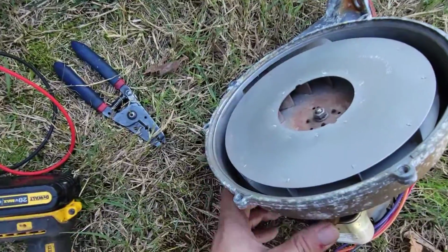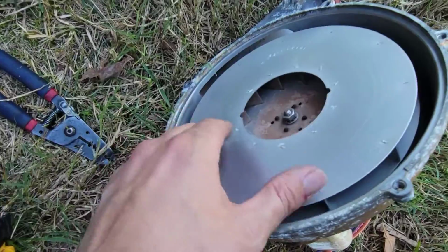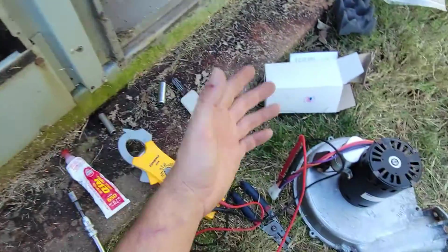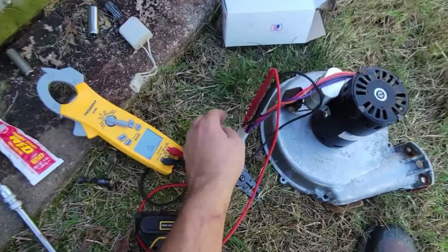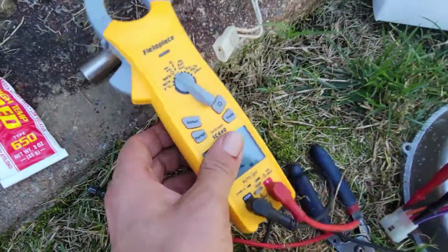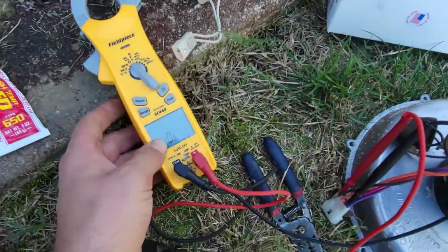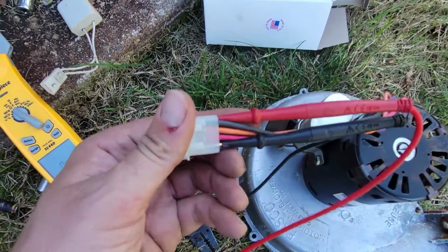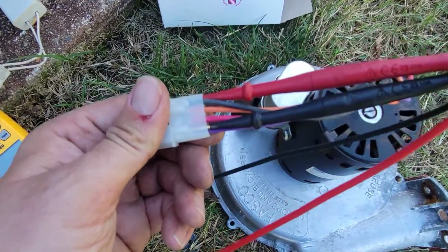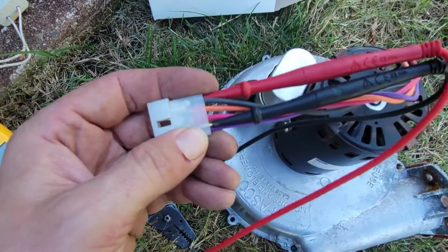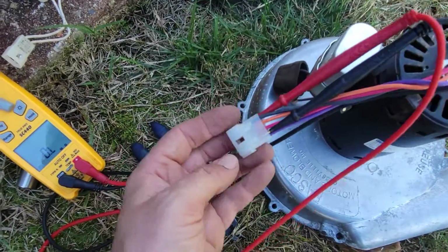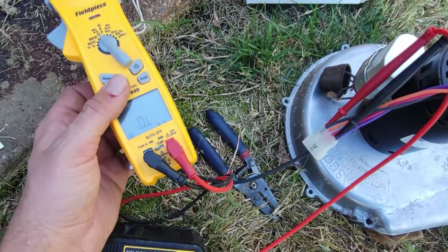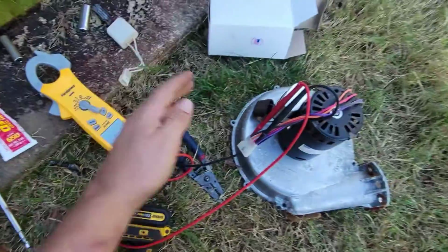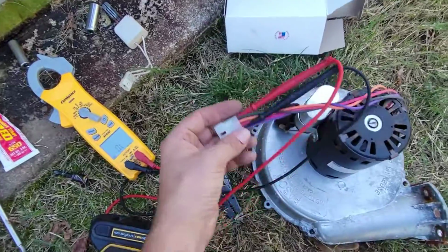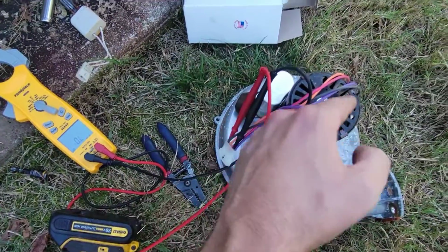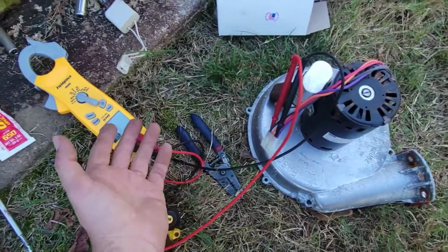But first, I'm going to show you this motor. This is the old motor, spins just fine. So how do I know the motor's bad, the old motor? So what I did was I took my meter, I put it on ohms, and I decided to measure the lines. So the line connection for these windings is black and purple. Okay, and I'll show you that on the diagram. But black and purple, I got my leads in there, and it's OL. We're not measuring resistance. That means our windings are open for the motor, and even though we have power going to it, the motor's not spinning because we have an open circuit.